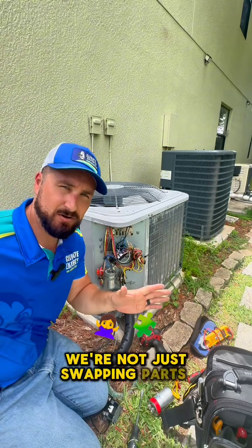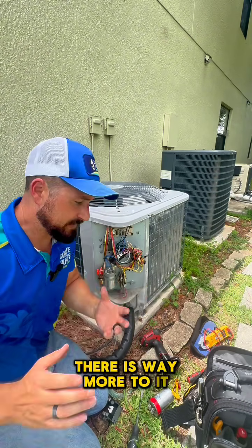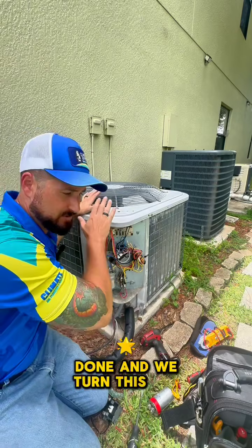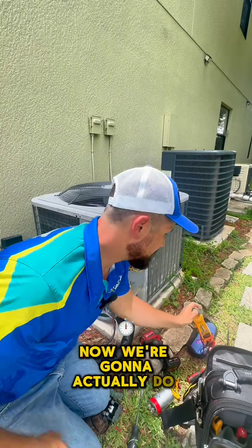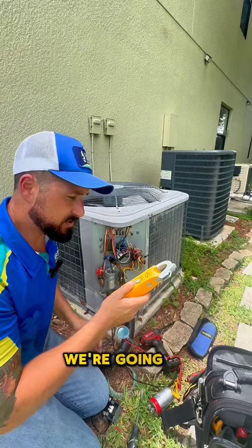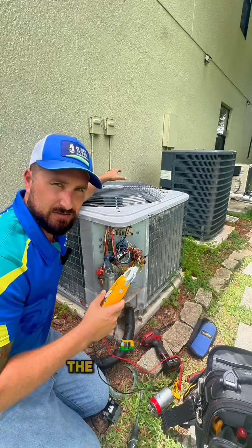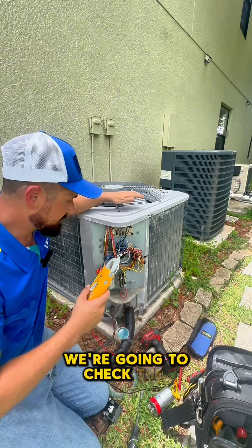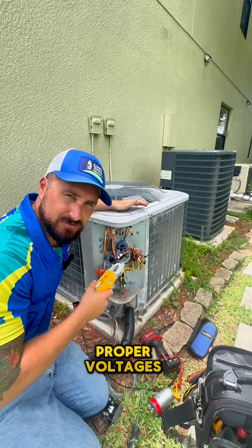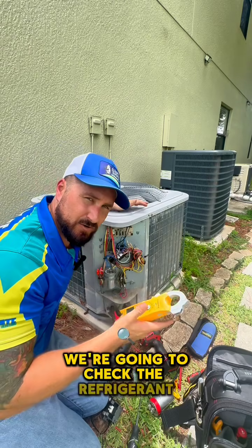We're not just swapping parts, okay? There's way more to it. And then when this is completely done and we turn this all back on, now we're going to actually do some run tests of this unit. We're going to check the amperages of each motor, the fan motor, the compressor. We're going to check the voltages to make sure it's sending the proper voltages through the contactor. We're going to check the refrigerant pressures.